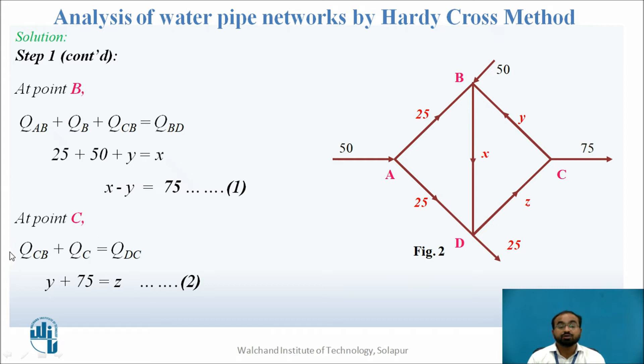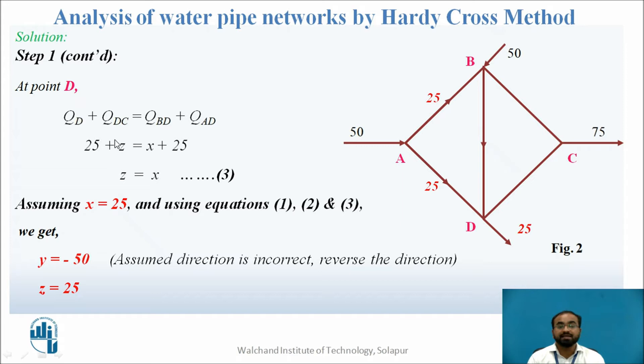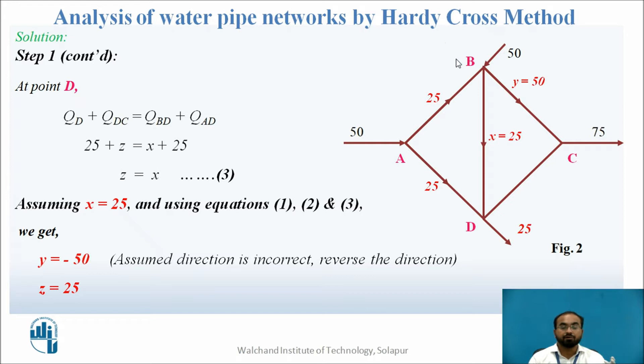At point C: Q(CB) plus Q(C) equals Q(DC), that is Y plus 75 equals Z. That is equation 2. At point D: Q(D) plus Q(DC) equals Q(BD) plus Q(AD), that is 25 plus Z equals X plus 25, so Z equals X — that is equation 3. Using these three equations and assuming X equals 25, I get Y equals minus 50, meaning my assumed direction is wrong. So I correct the direction: Y equals 50 and flow rate is from B to C, and Z equals 25.